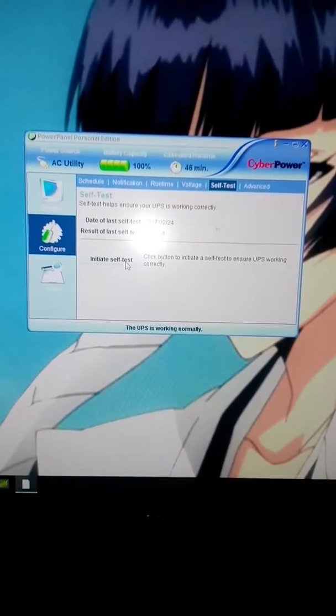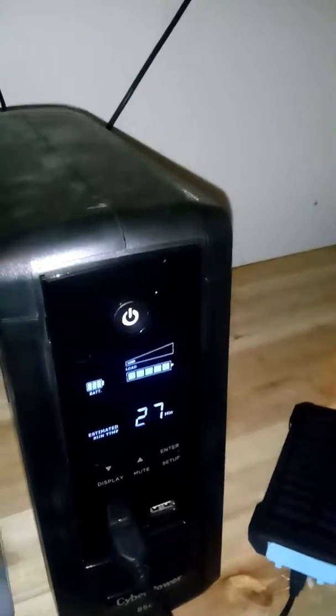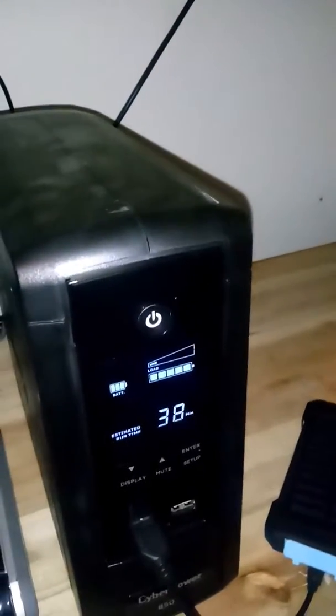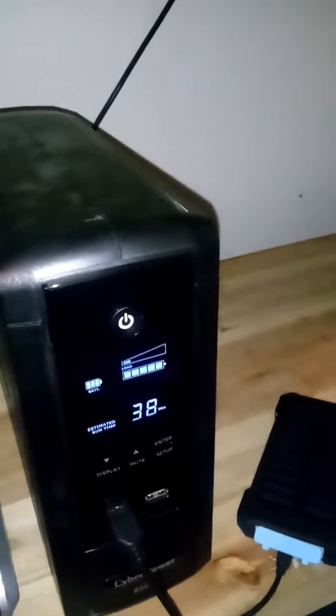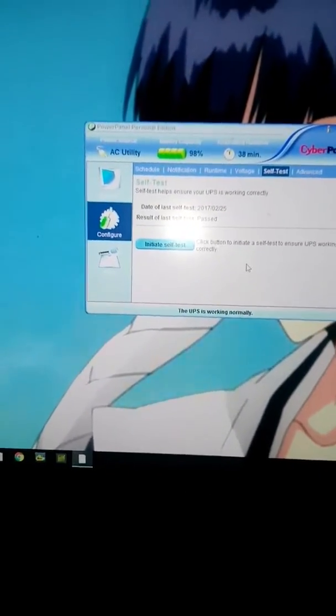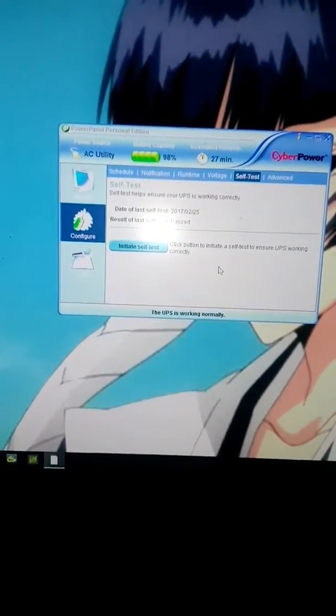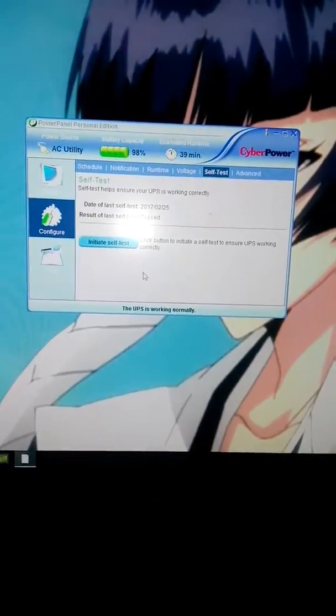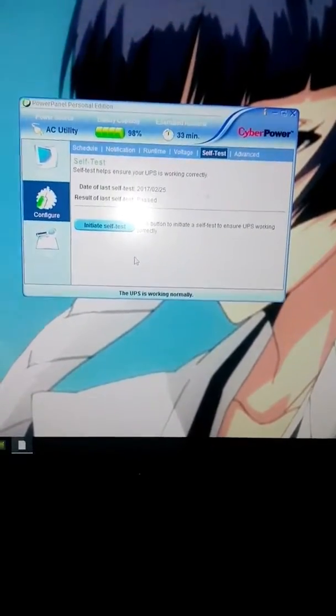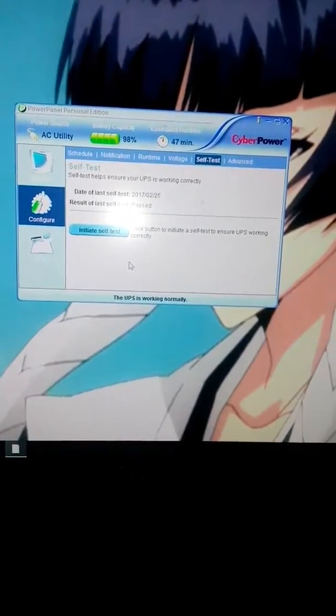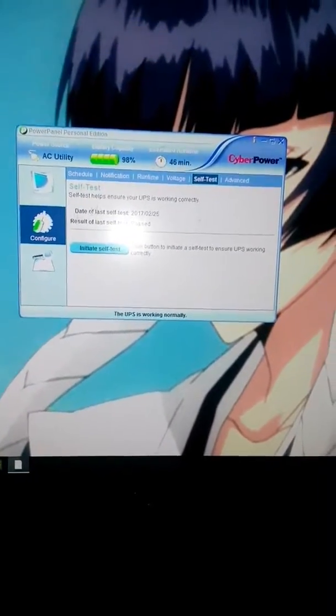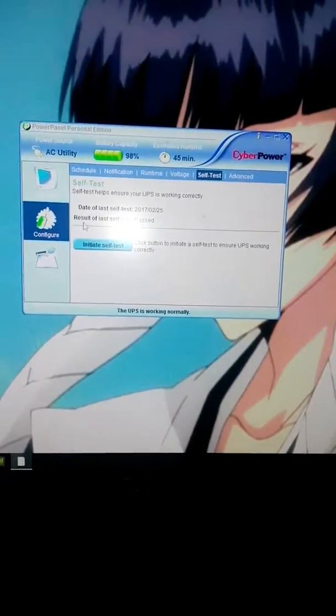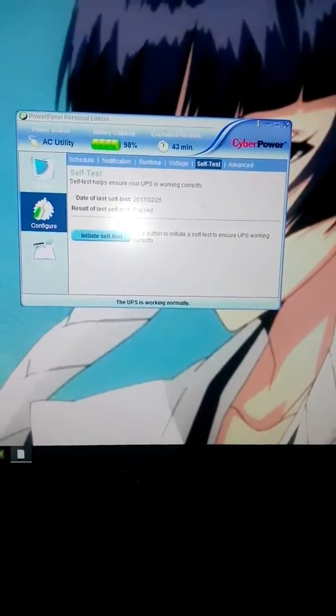Now, initiate self-test. You can hit initiate self-test and you'll see the UPS kick on to battery. Give it a second, and it kicks back on. What that basically does is allow you to test your UPS to ensure it's working, that there's no batteries gone bad, that it'll kick on and off when it's supposed to, when the power drops or whatever. You can see the date of last test was just yesterday, and the result of last test, which was just now, was it passed.